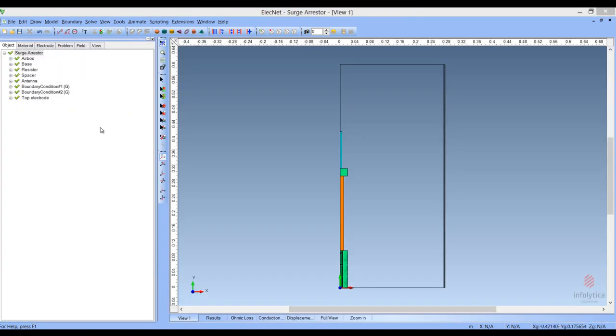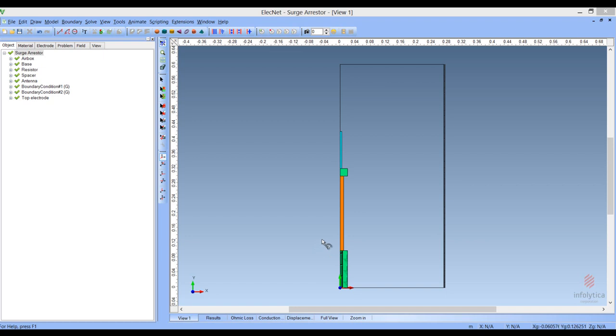The last application we'll examine today is the surge arrestor — in particular, we'll be looking at the surge arrestor under lightning strike conditions. I have brought up the surge arrestor on the screen. We have the antenna and base, which are conducting and will form our high voltage electrode. We have the resistor stack, which will act as a variable resistor to the voltage. Down at the bottom we have the pedestal, which will also be set to ground potential. We will be looking at a 2D model of the surge arrestor, because the symmetry of the cross section is symmetric by revolution — any plane cut through it at any angle will look exactly the same.